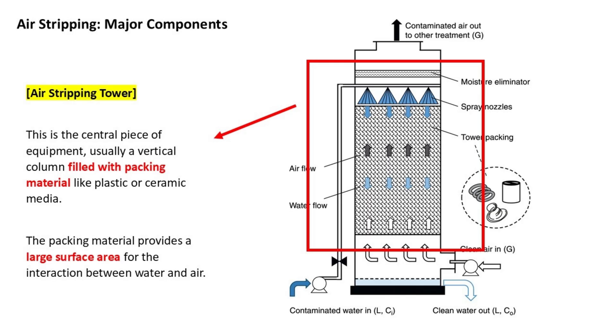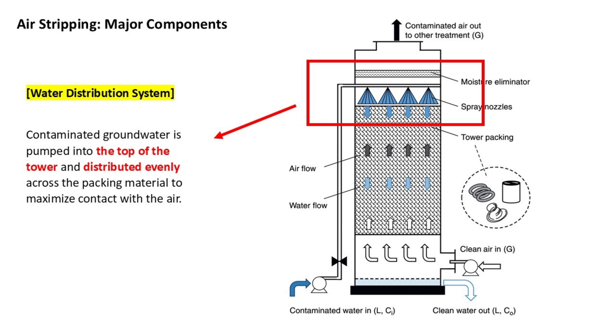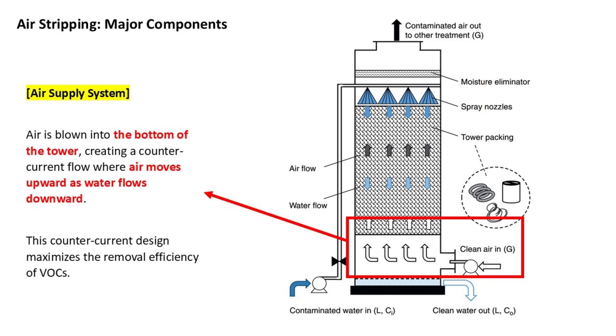Now let's take a look at the major components of a typical air stripping system. The air stripping tower is the central piece of equipment, usually a vertical column filled with packing material like plastic or ceramic media. The packing material provides a large surface area for the interaction between water and air. The water distribution system pumps contaminated groundwater into the top of the tower and distributes it evenly across the packing material to maximize contact with the air. The air supply system blows air into the bottom of the tower, creating a counter-current flow where air moves upward as water flows downward. This counter-current design maximizes the removal efficiency of VOCs.